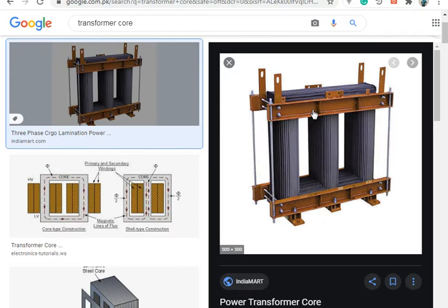So when a short circuit happens, the forces are either going to crush the core, or they are going to blow the windings outwards. The same thing happens for the core also. Now I am talking with respect to the core. The core has eddy currents. Those eddy currents are inside the magnetic field, B, which is already being produced over there. So those cores or laminations are also moving or vibrating. There is a specific word used for it. I am not going to use that word here.